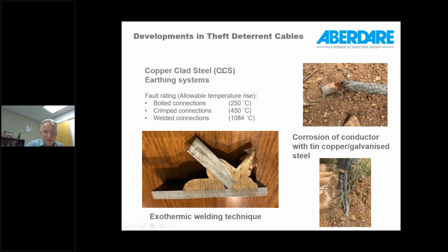So copper-clad steel earthing systems, the fault rating depends on the allowable temperature rise. Of course, when you calculate fault rating, it relates to the time duration of the fault. It relates to the start and end temperature, and it also relates to the properties of the material and the size, in essence the resistance of the product. But it also depends on the type of connection that is made.